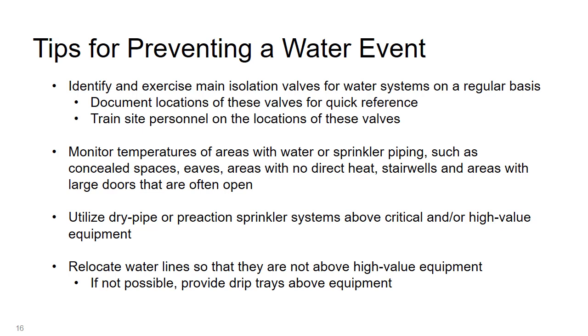By quickly shutting off these valves, it eliminates guesswork that may take place if facilities personnel try to locate the local isolation valve in an emergency situation. Of course, there's little value in knowing the location of the valves if you can't close them. That's why regular, typically annual, exercising of these critical valves should be performed. This ensures that they are not seized in the open position and they can travel fully into the closed.